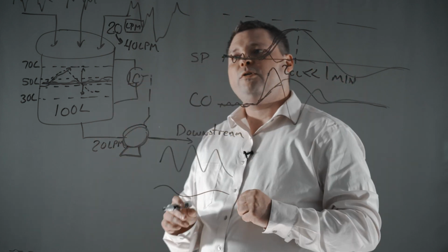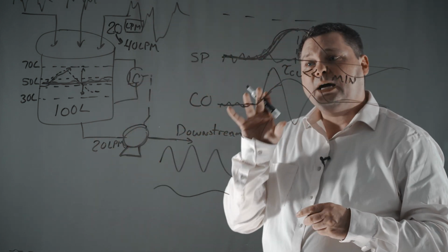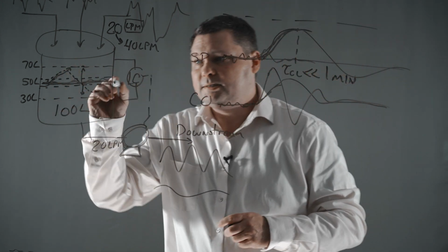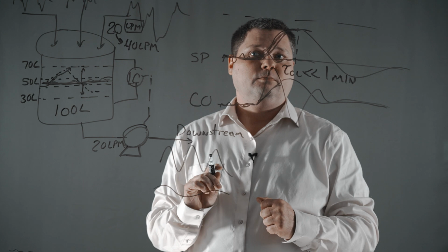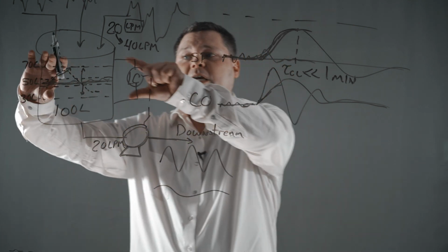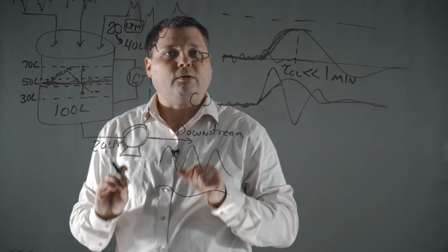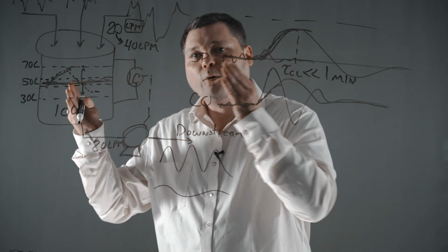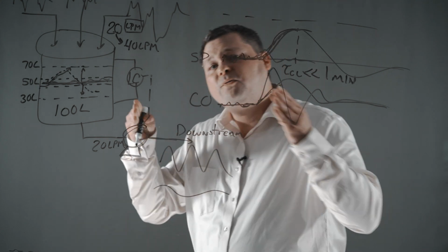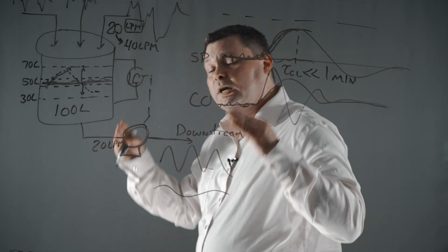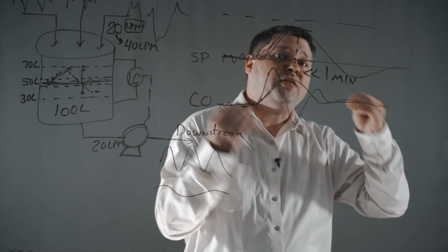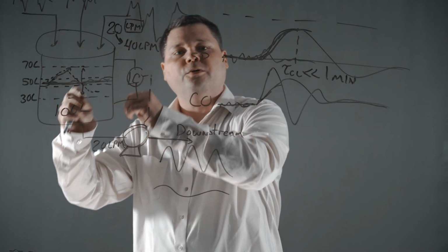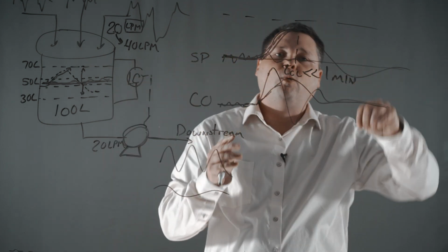So when you're looking at a level controller, you really do want to spend the time and define the objective. How tight of control do you need? Is this a surge tank or is this a steam drum, right? Those are going to have different objectives and different tolerances that are allowed. How big is this tank? Is this tank 50,000 gallons or 50 gallons, right? You're going to approach a 50-gallon tank with high flows a little bit more aggressively than a 50,000-gallon tank. Right? So understand the size, the scope, the flows, so you can start to understand the time requirements for the speed of the process.